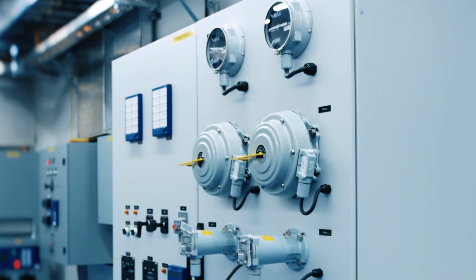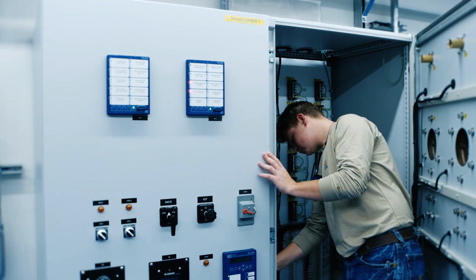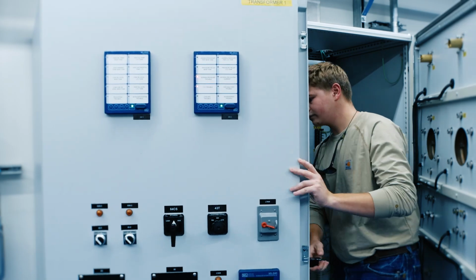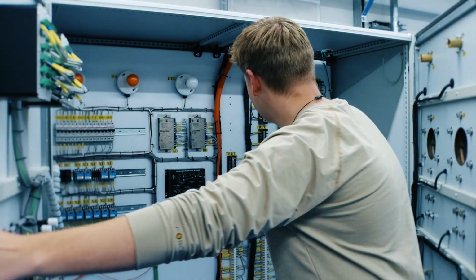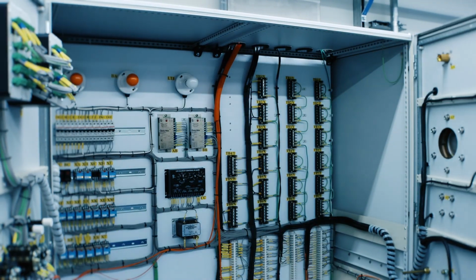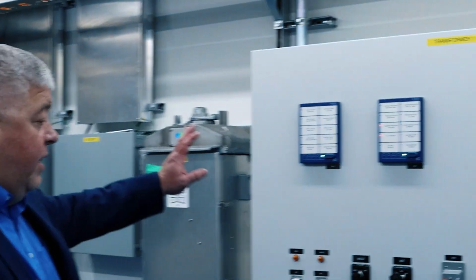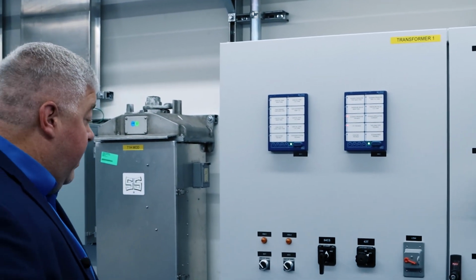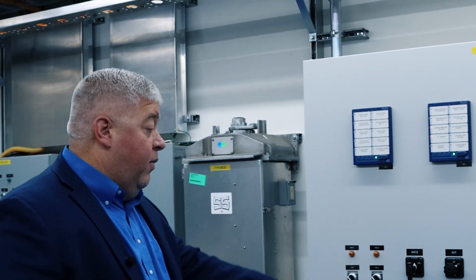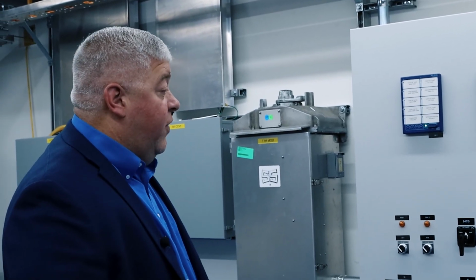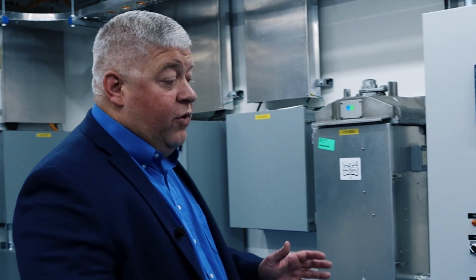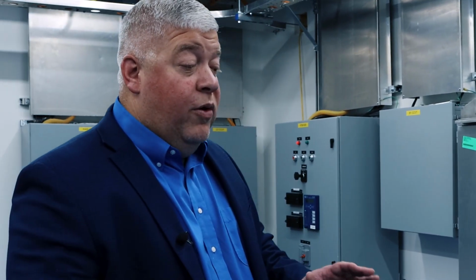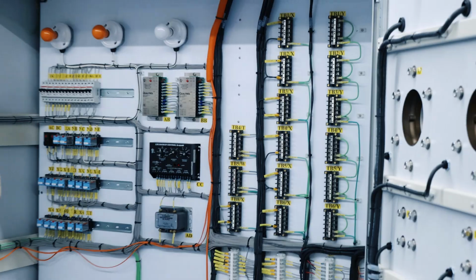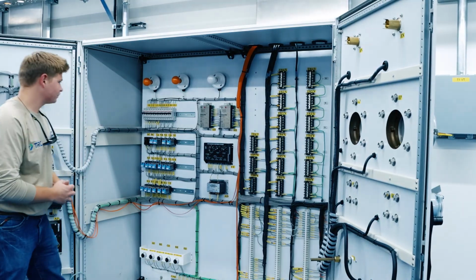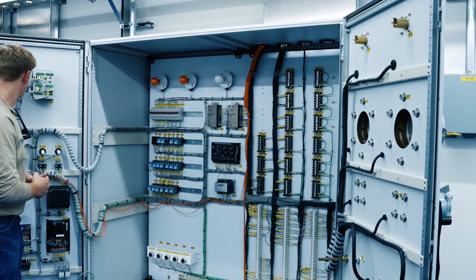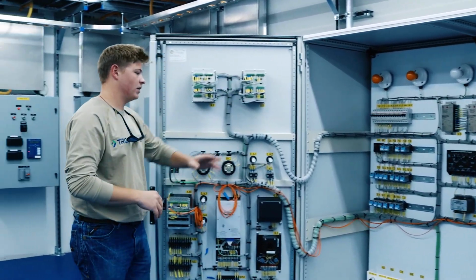One of the things we're most proud of is our transformer simulator. We've taken many of the devices someone would have to commission in the field and tied them into an alarm system. We have load tap changers, a relaying device, and a control device, and the individual can come up here and learn how to do most of the tests associated with a transformer in a controlled environment. It's really something we designed and we're very proud of.